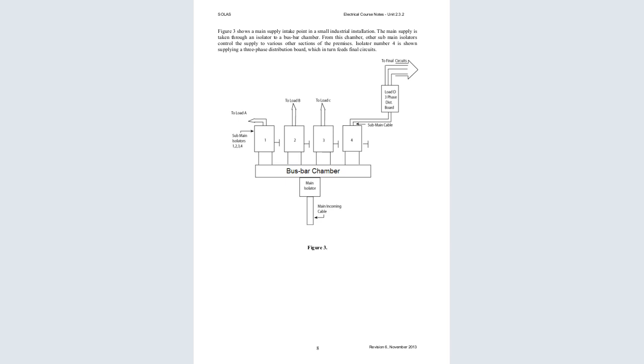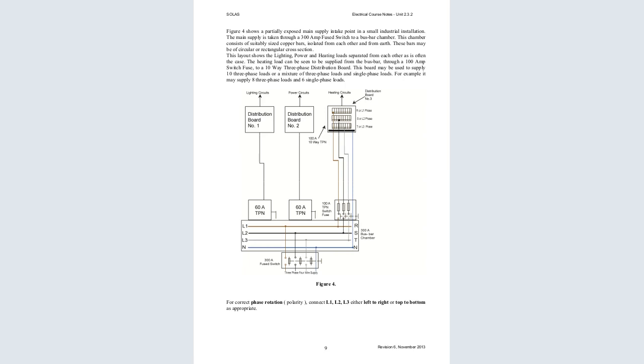Isolators are switches or protective devices, where we have the fuses and the switches that are able to break the circuits or cut off power in case of any danger or in case power is not needed. That is the control circuits. So those are what we mean by isolators. Isolators are like main switches that are used to cut off power. Okay, we proceed.